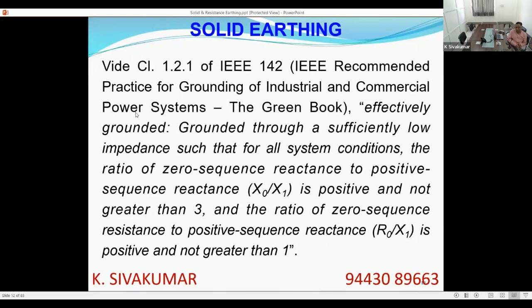Effective earthing, they say, is a system of earthing in which the zero sequence reactance to positive sequence reactance ratio is less than 3. That means the earth fault, zero sequence reactance or earth fault loop reactance is very less. Similarly, the zero sequence resistance to positive sequence reactance ratio, the resistance in the earth path, the zero sequence path, is also not greater than 1. At the maximum, it is equal to the system positive sequence reactance, or many times it is much lesser. So to be qualified as an effectively earthed system, these two conditions are a must. The ratio of X0 by X1 should be less than 3, and the ratio of R0 by X1 is less than 1. So this is the proper definition of an effectively earthed system, but unfortunately this appears in the American IEEE standard, not any Indian standard.